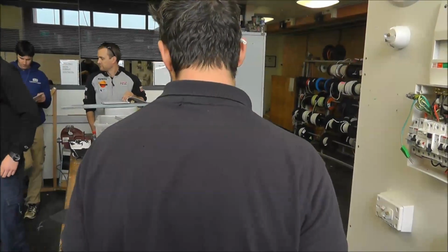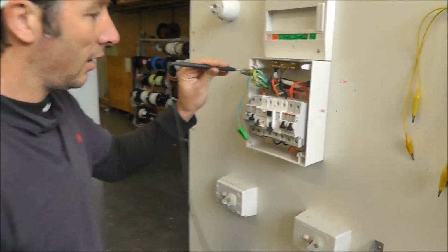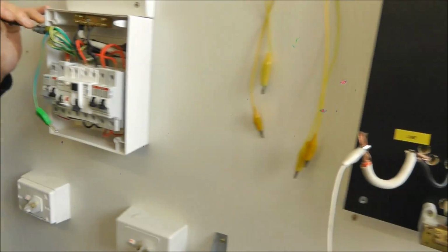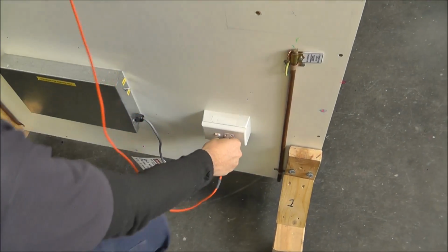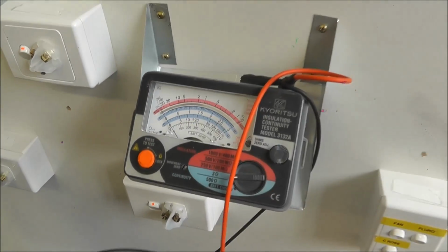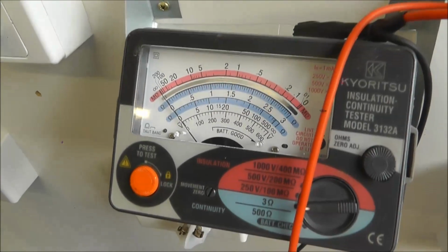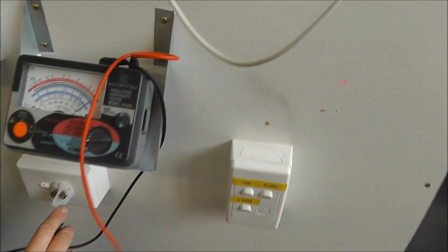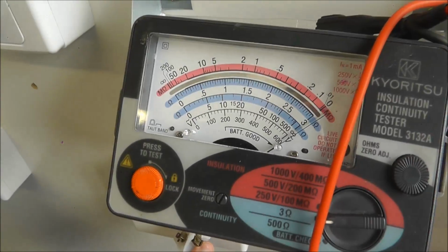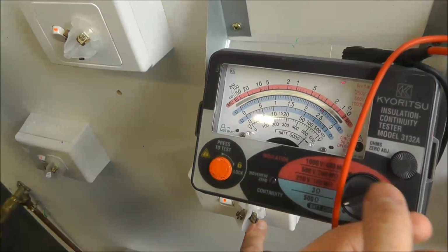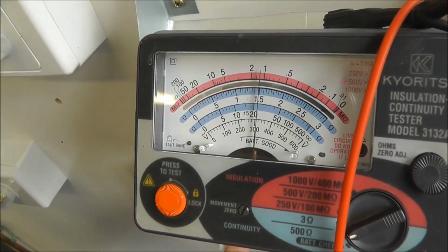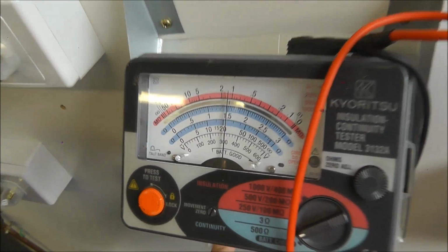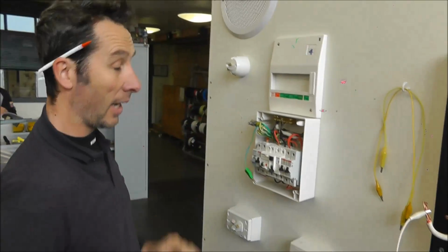Next thing I've got to test is socket outlet 1. In between here, I don't know what socket outlet is what. I think it's there. One's down the bottom. I'm on the 3 ohm scale, so that's pretty much 0. And socket outlet 2, over here, this one will do that. Flick on to 500 for me, Dobbo. Thank you. We've got 20, is it? Yeah, 21, something like that. Okay, so I've got them down.